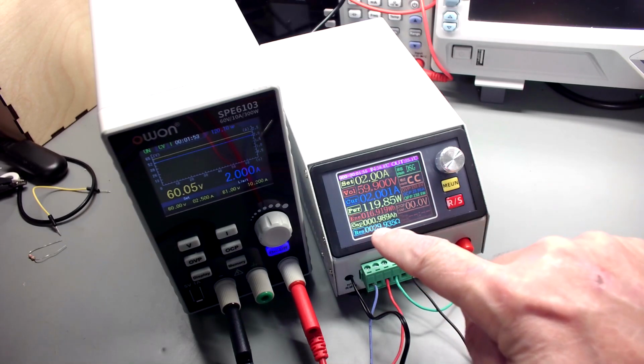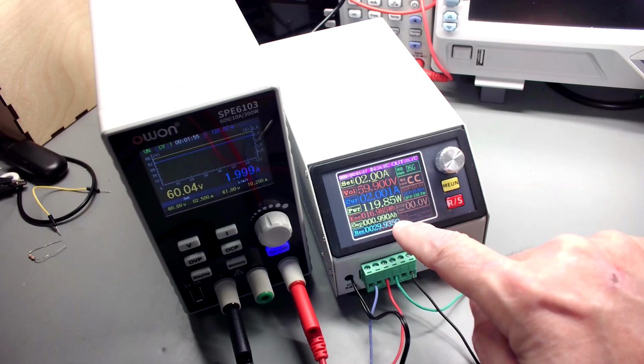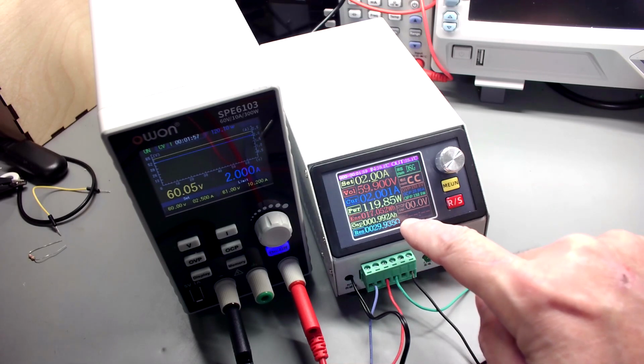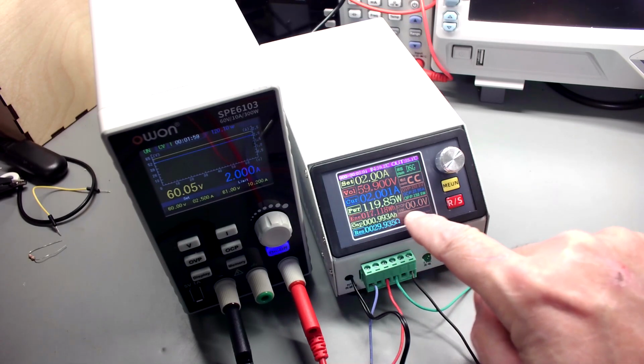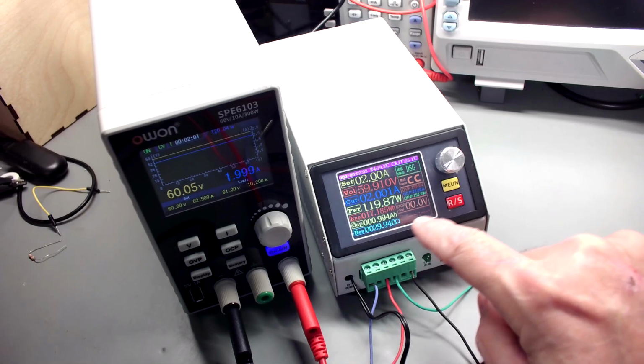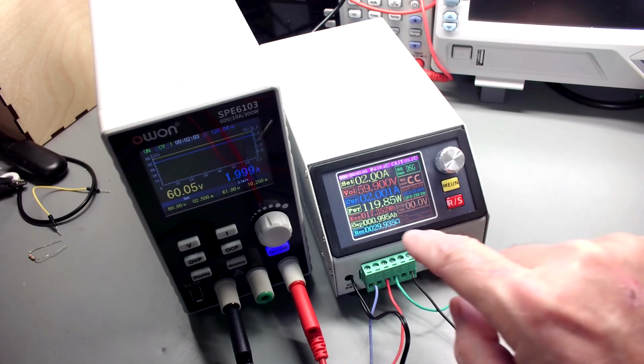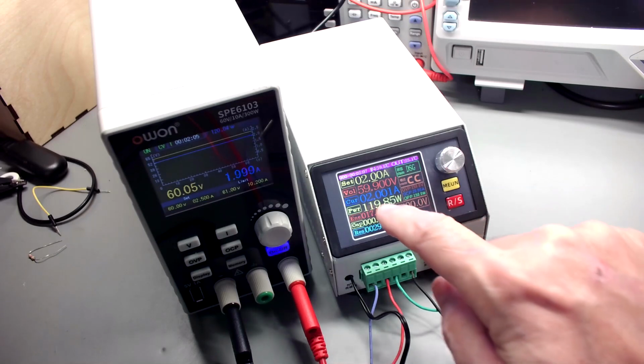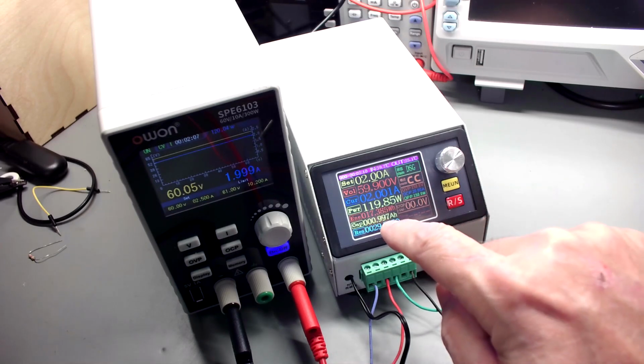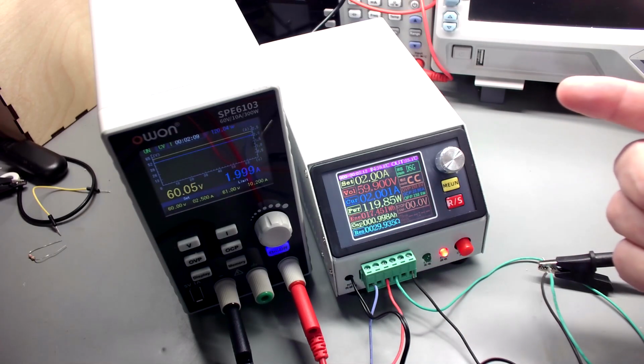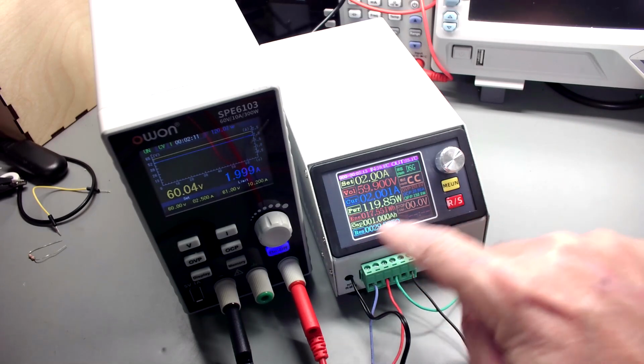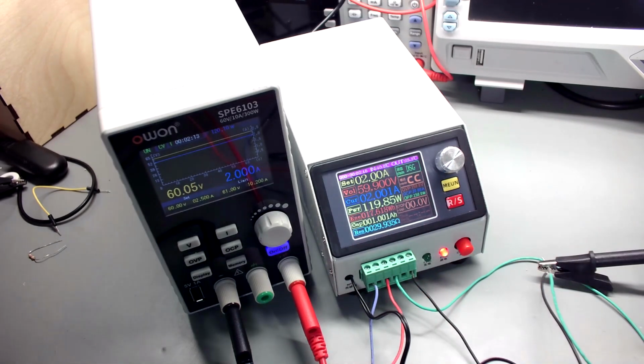This tells you how many amp hours capacity it has. So as you run a battery down, you set a stop voltage right here - the lowest you want your battery pack to get down to. You reset this, and when you start the test at whatever load, it's going to count up how many amp hours that battery had. That's what it's useful for.